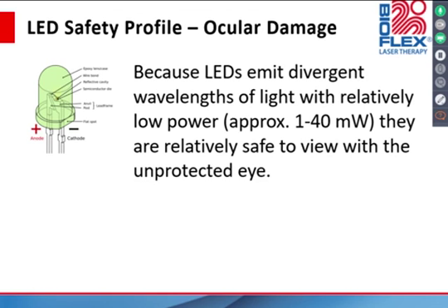So when you're using our equipment, you don't need to protect the eyes against the LEDs using the arrays. The only time that we do say to use the safety glasses with the LEDs or the arrays is if you're using the arrays very close to the face or the eyes. Although that light won't harm the eyes, it is very bright, and that patient might find it quite uncomfortable.